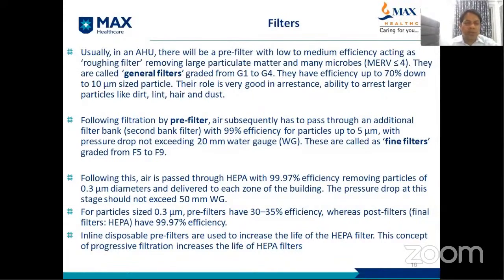Second, after the pre-filters or general filters, the air subsequently passes through additional filter banks, a second bank of filters with 99% efficiency for particles up to 5 microns, with pressure drop not exceeding 20 mm water gauge. Pressure gauge is important. These are called the fine filters. Then the third category is the HEPA filters. The pressure drop at this stage should not exceed 50 mm water gauge. For particle size 0.3 microns, pre-filters have 30 to 35% efficiency, whereas post-filters, the final HEPA filters, have 99.97% efficiency.